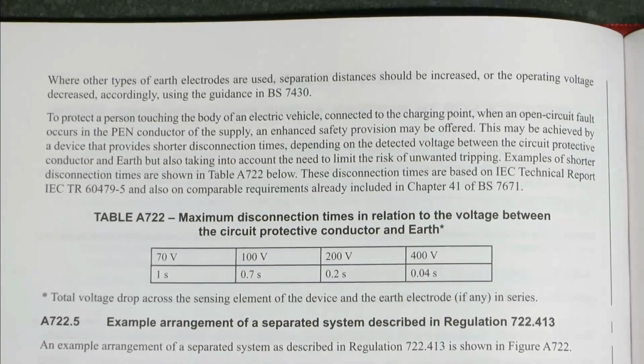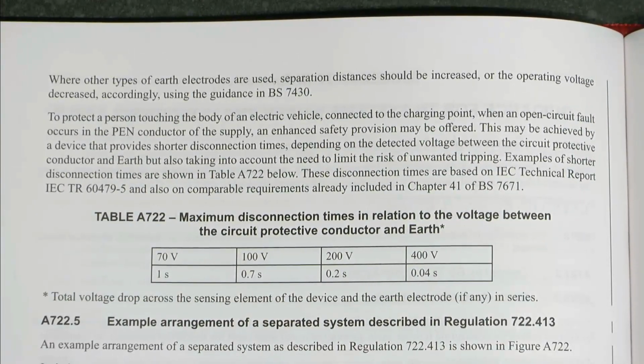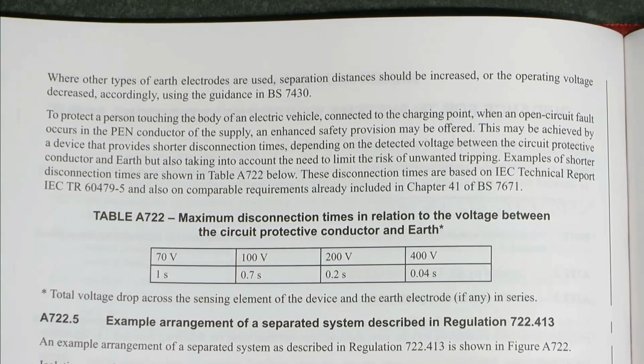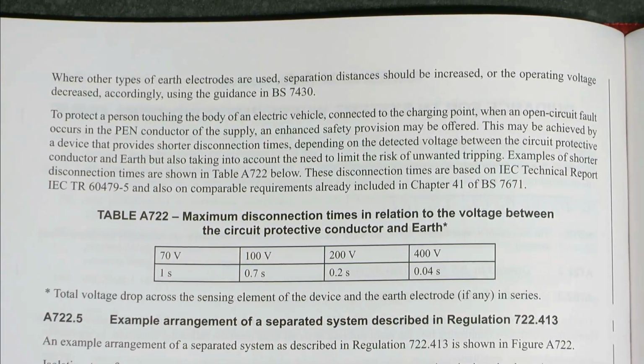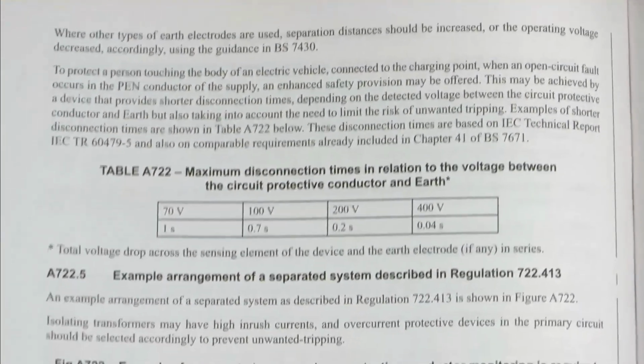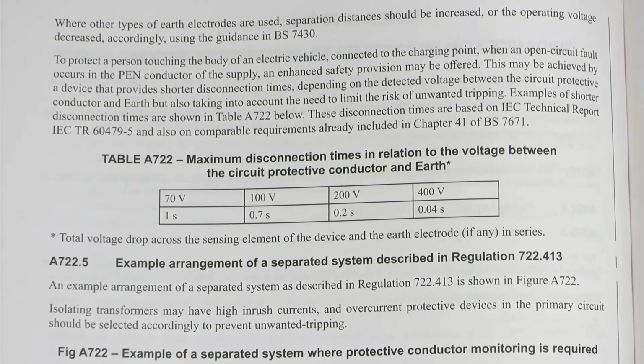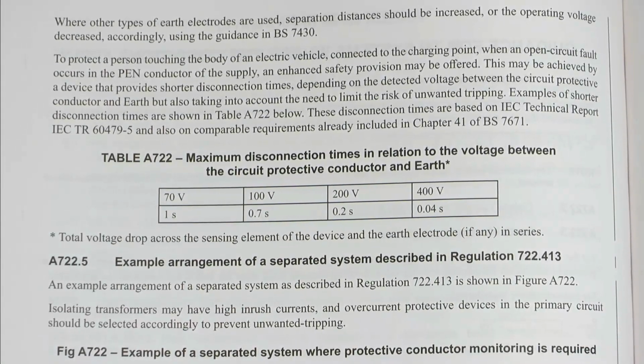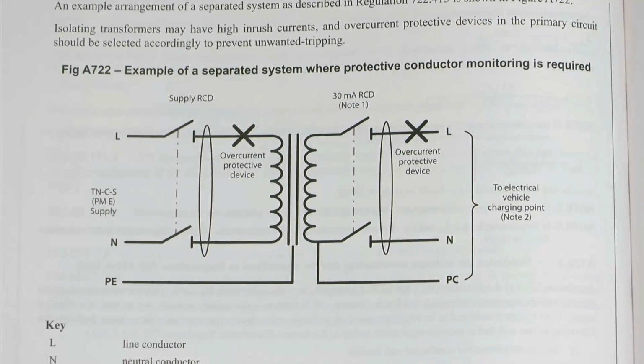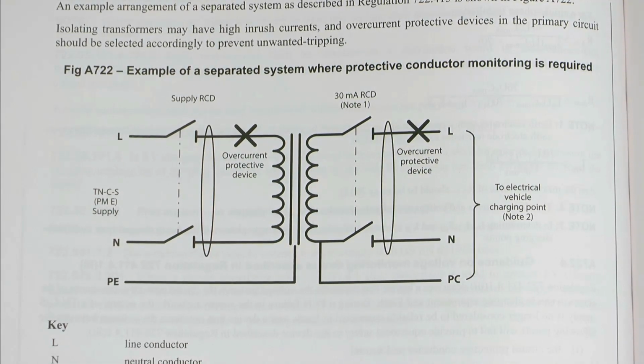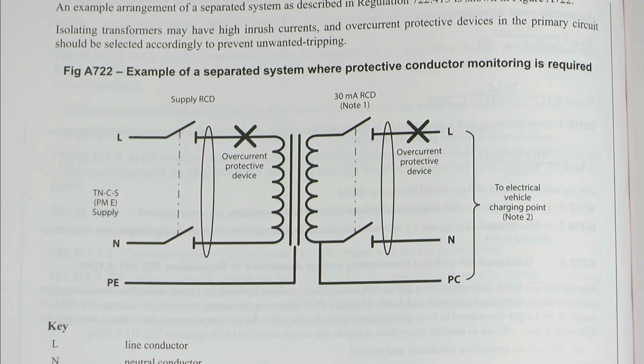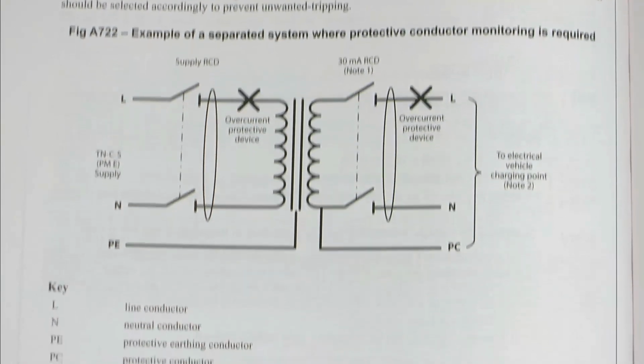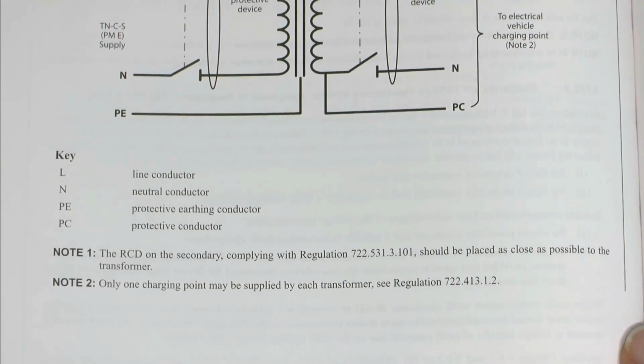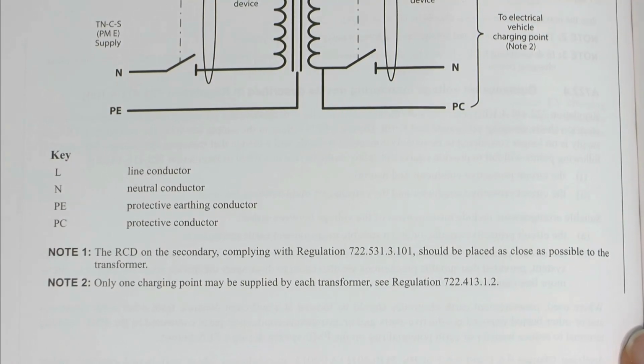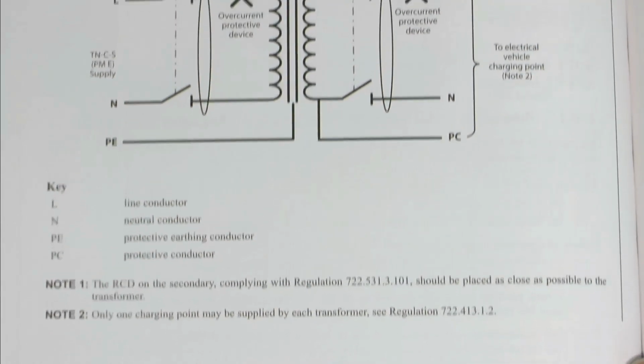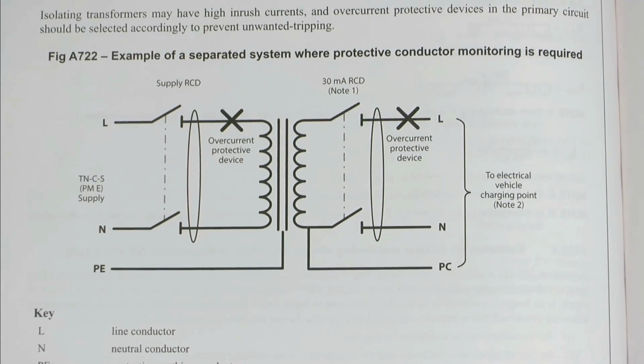And over the page here we've got a continuation of that. It gives you some examples of maximum disconnection times in relation to voltage between the circuit protective conductor and earth, so anything from 1 to 0.04 seconds depending on the voltage level. And there's an example here of how this could actually work where protective conductor monitoring is required. Again, this is all very unlikely to be used in reality, but say if you do want to use it, then it's available here to be used.